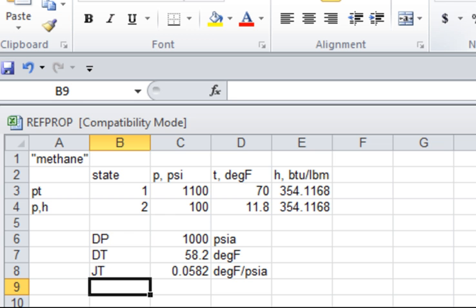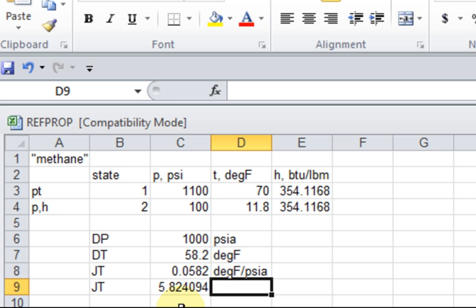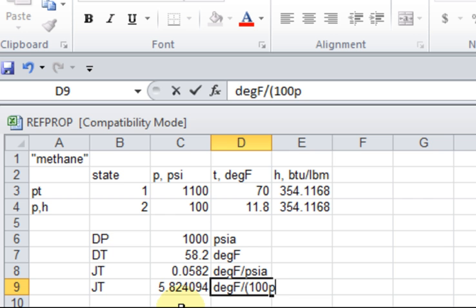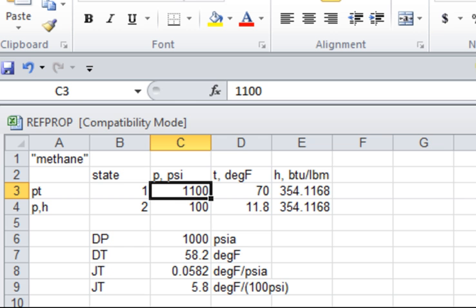That's not so pretty because it looks like that. What I want to do is report the Joule-Thomson just like the natural gas association did, in degrees F per 100 psi. See the difference. So it looks like these values are coming in right at 5.8. What did it say it was, around seven? So it's close but not spot on. In their glossary it said it was around seven degrees F per 100 psi. What you can do is start changing things. Let's say it went from 300 psi to 100 psi. Well that's now 5.6.